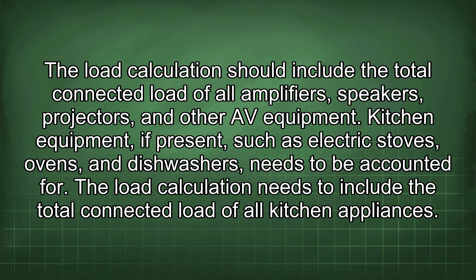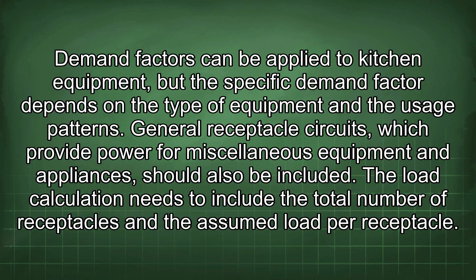Demand factors can be applied to kitchen equipment, but the specific demand factor depends on the type of equipment and the usage patterns. General receptacle circuits, which provide power for miscellaneous equipment and appliances, should also be included. The load calculation needs to include the total number of receptacles and the assumed load per receptacle. The NEC provides guidelines for determining the load per receptacle based on the type of occupancy.